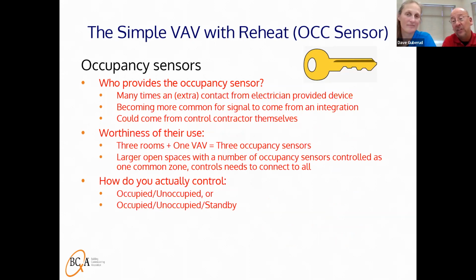Are there multiple contacts on that occupancy sensor for the control contractor to jump onto? We're seeing more and more lighting integration. So can the control contractor just go to the integration and find out the zone occupancy signal, or might the control contractor themselves have to provide that occupancy sensor? Right, and then is it worthy of even using an occupancy sensor? Sometimes we're having multiple customers these days say, hey, we've got 3 rooms or 3 exam rooms or 3 offices on one zone. And all 3 of those rooms have to go unoccupied in order for that VAV box to go unoccupied. Especially if they've got a high rate of patients, or if those rooms are occupied very often, they're questioning the benefit of the limited unoccupied time, because there's virtually never not a person in one of those 3 rooms, right? So talking through that and understanding the use of their space and the benefits of this to their space.